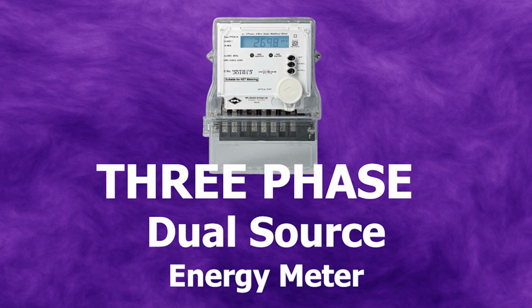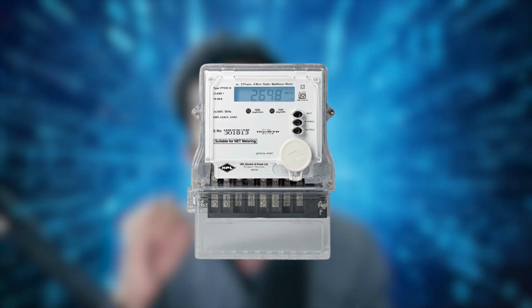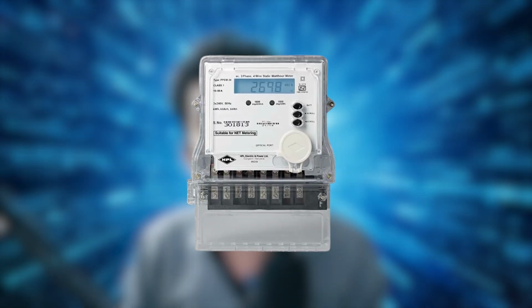Second one is the three-phase dual source energy meter. When we are talking about factories, hospitals, or data centers, that is where this three-phase dual source energy meter comes into the picture. These meters are built to handle full 415 volt or even higher systems, and they measure energy flow separately in three lines of electrical R, Y, B. They also offer more advanced diagnostic features like power factor, load profiling, and energy logs per source. So whether it's a small shop or a full-blown industrial city, there is a type of dual source energy meter for it.